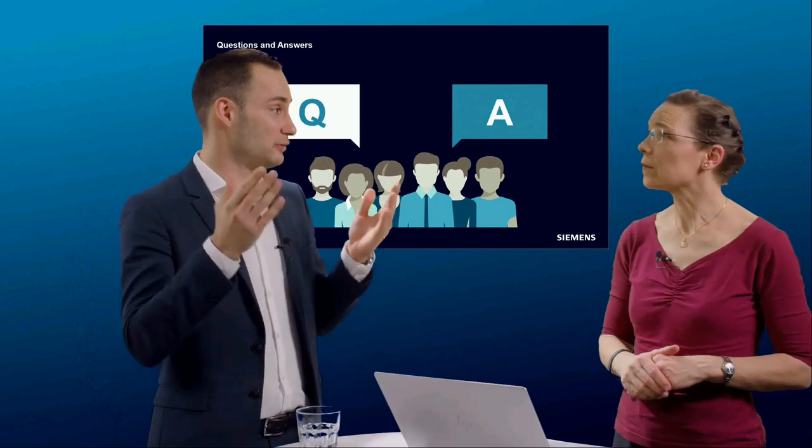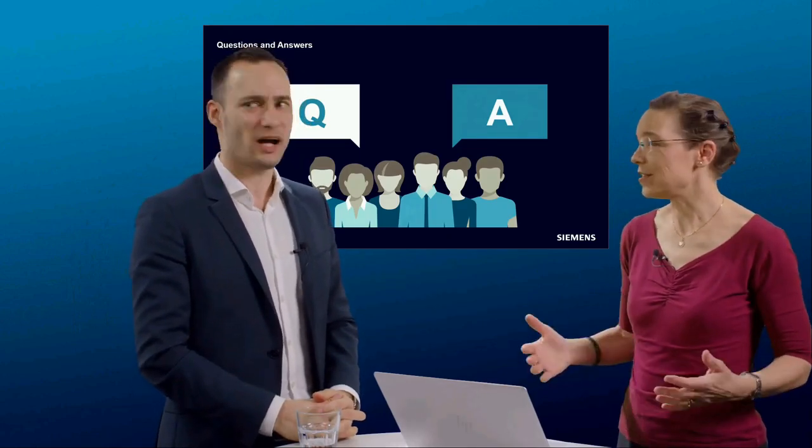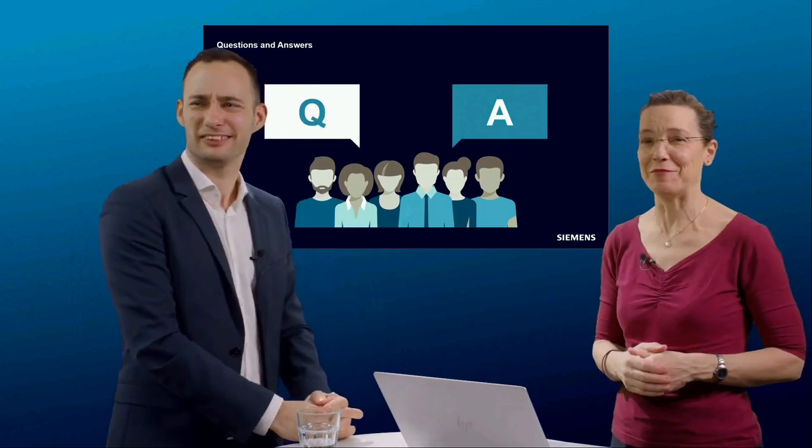In the past, we had two different standards which could apply or not for the equipment when it was used together with the GCB. Today, going with a module, I can answer this question directly. You use the GCB standard because that's the one used for the GCB module and system. It's one, not to use the term headache, but one more piece of work for our customers, consultants or engineers to think about: which one do I have to use? This is type tested, it has worked together. Look at the IEC and IEEE standards, it's compliant with both. So just go the easy way and take the complete type tested system.